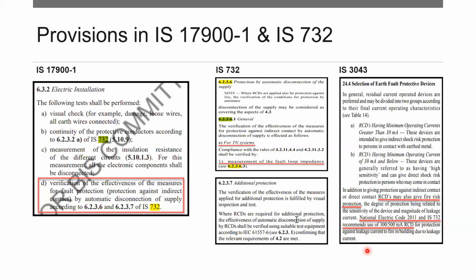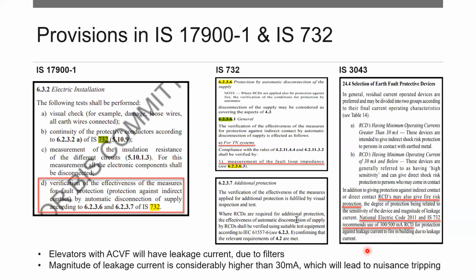Now, as Mr. Gopakumar was also explaining earlier, the currents in case of the elevators can go above 500 milliamps in certain cases, and it can reach up to 1000 milliamps. Because the elevators of the modern day have ACVF, which have leakage current due to filters, and since the magnitude is higher, the 30 milliamps RCDs could trip, and this will cause nuisance tripping, leading to operation malfunctioning or operation issues of the elevators.